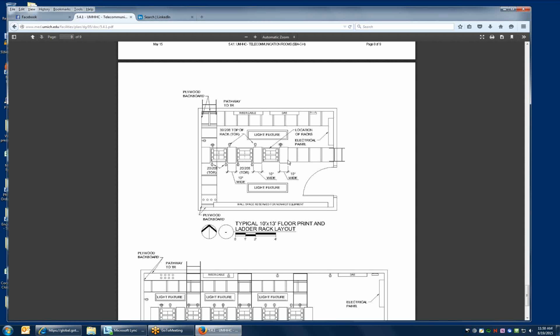We're doing 10-inch wire management now for the amount of data. We've got our cable tray around the room. We've got the wall space reserved for non-MCIT equipment. That's your nurse call, your distributed antenna system stuff, any specialty systems that may arise. I did put DAS over here, actually. We have our riser cable. We have our conduits coming in.